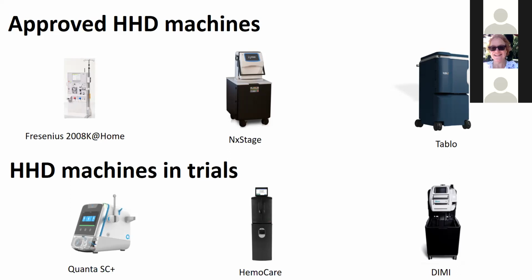The Tablo machine is really designed to be a very simple machine. It has a touch screen that walks you through every step of setup, treatment, takedown, and maintenance of the machine, so it's really designed to be easy for staff and patients to use. And instead of using packaged or batch produced dialysate, it produces the dialysate on demand from the home's water source. Different from the Fresenius machine, the water treatment unit is all in the bottom part of the machine. It doesn't require a whole separate water treatment unit. So it's a little bit less intensive than the Fresenius machine in terms of what has to go into the home for water processing. So, potential advantages there.